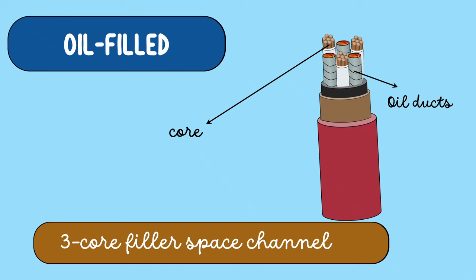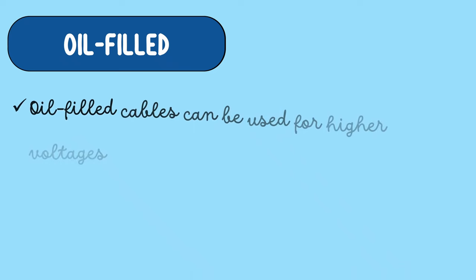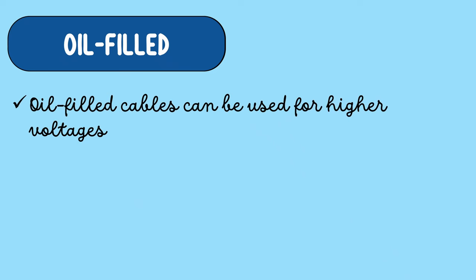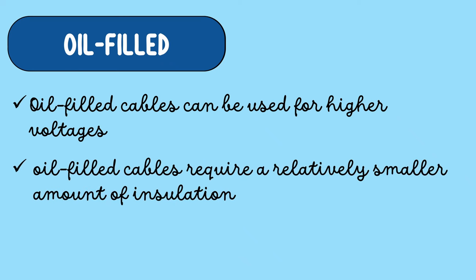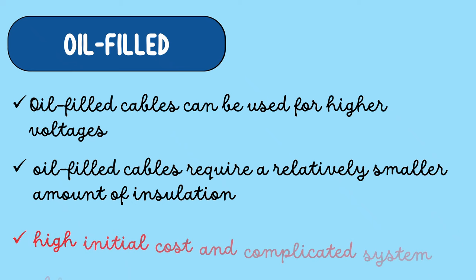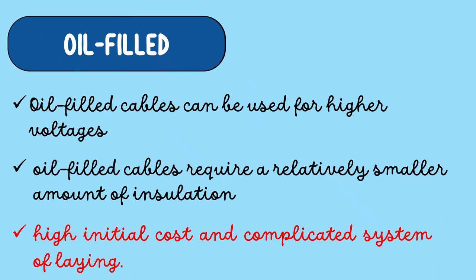Due to the elimination of voids, the oil-filled cables can be used for higher voltages. The oil-filled cables require a relatively smaller amount of insulation as compared to the solid type for the same operating voltage. However, their major disadvantages are the high initial cost and complicated system of laying.